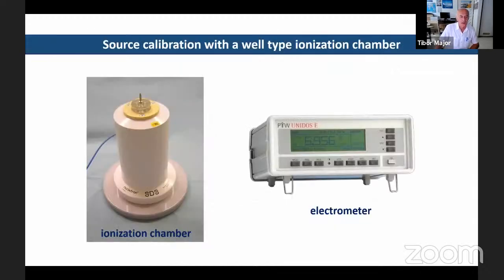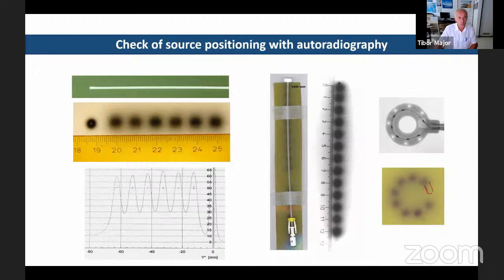The source has to be calibrated after the replacement, and these are the equipments which can be used for the source calibration. There is an ionization chamber on the left side and the electrometer. In the practical video, you can see more details about the source calibration. The source positioning accuracy has to be also checked. Here you can see the images using autoradiography.